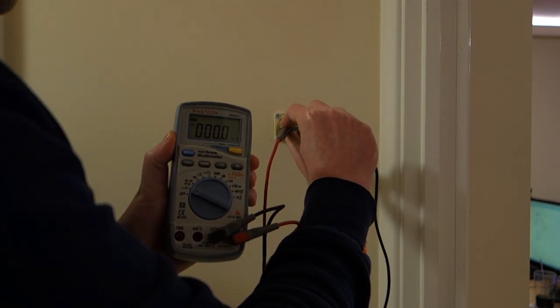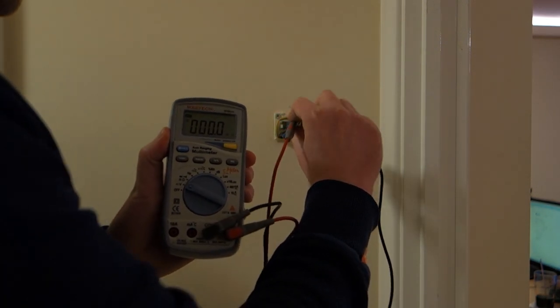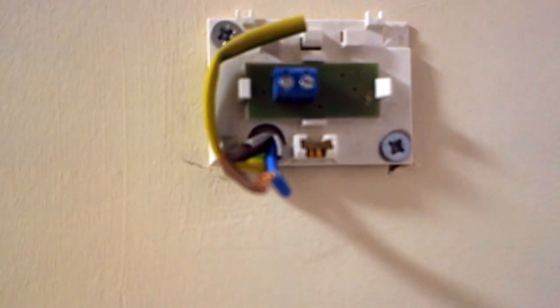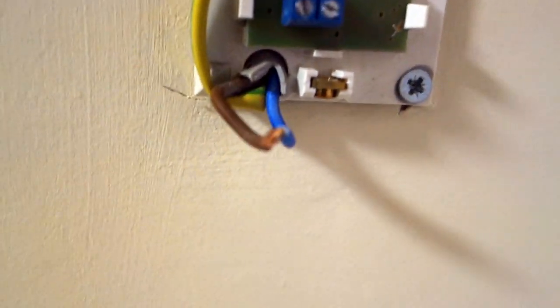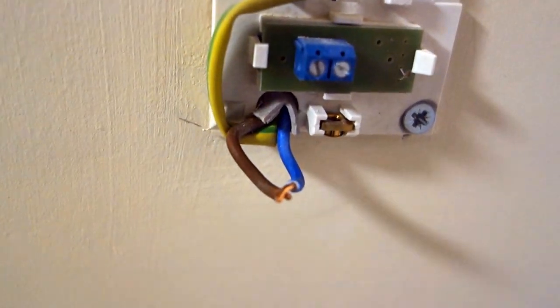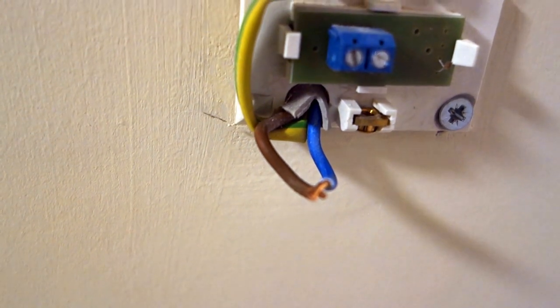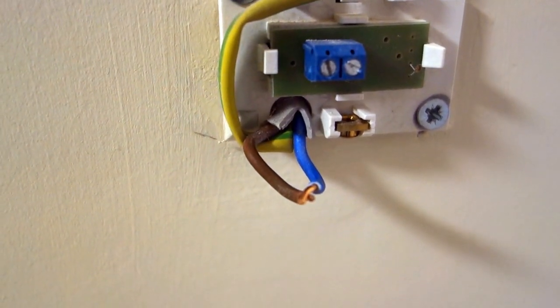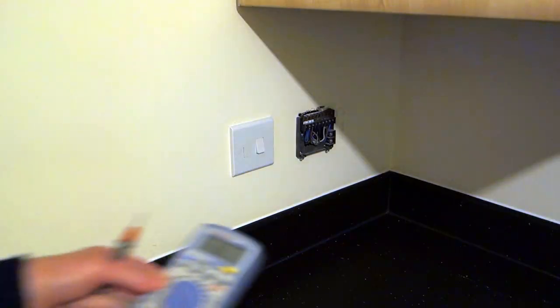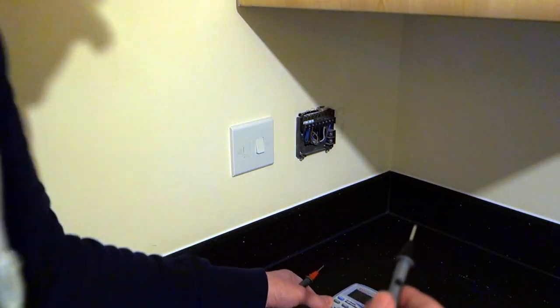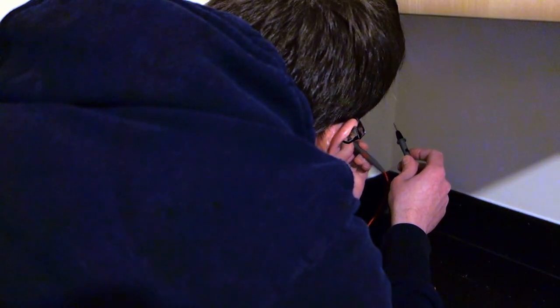Now we're going to make sure that the wires coming out of the thermostat are the same wires going into the programmer. So we're going to loop them over each other after unscrewing them, and then go back to the programmer and do a continuity test to see if we can make a circuit. If we've made a circuit, we know that the wires are completely related, and then we can remove them from the wall.